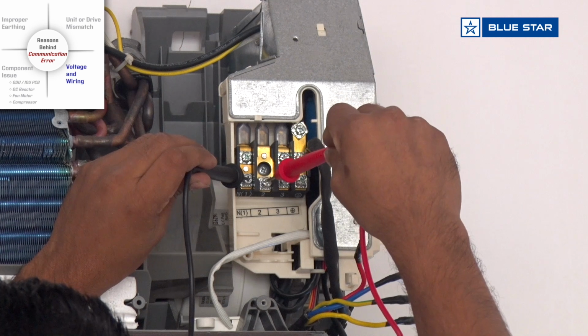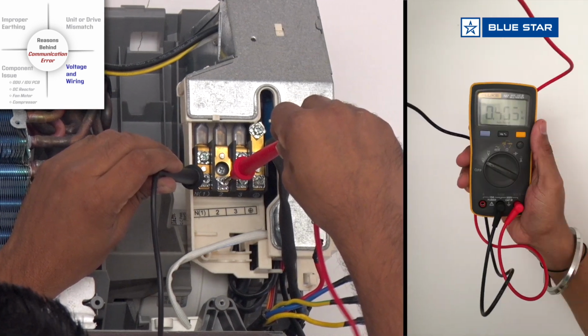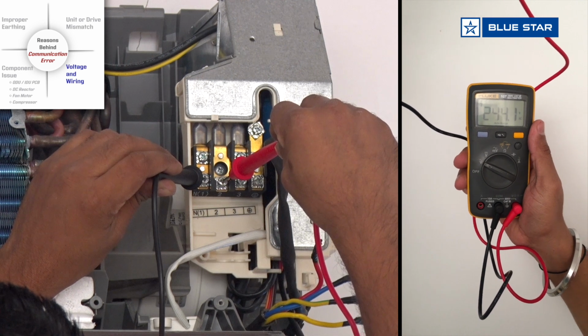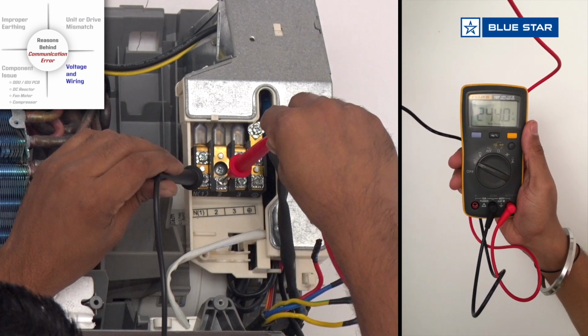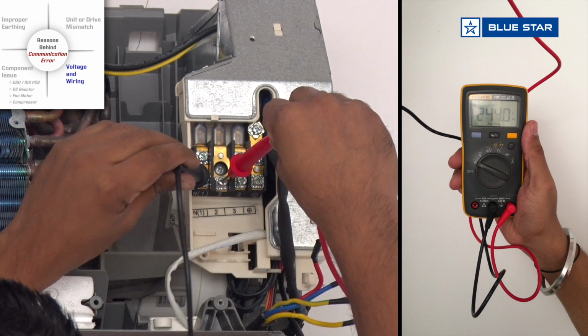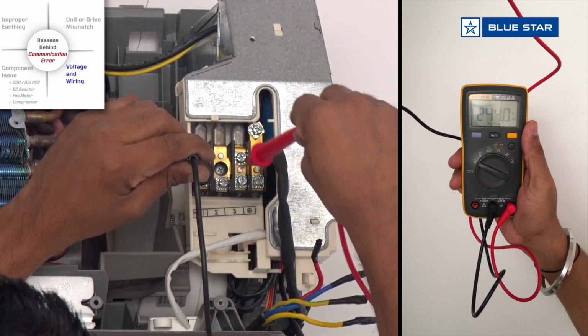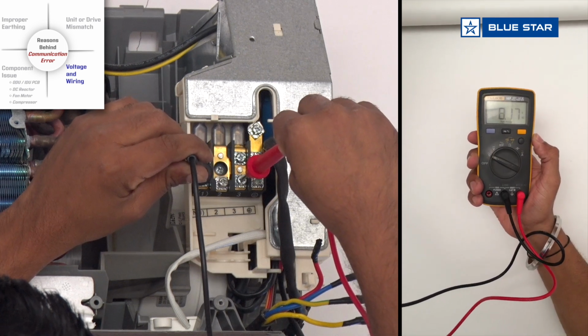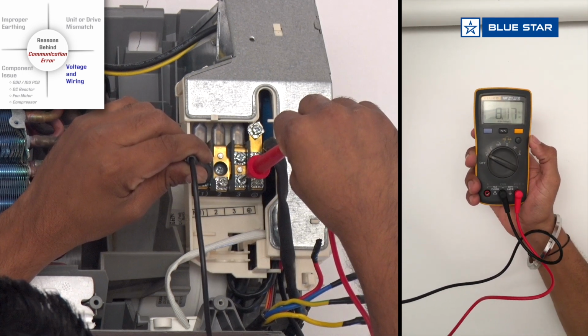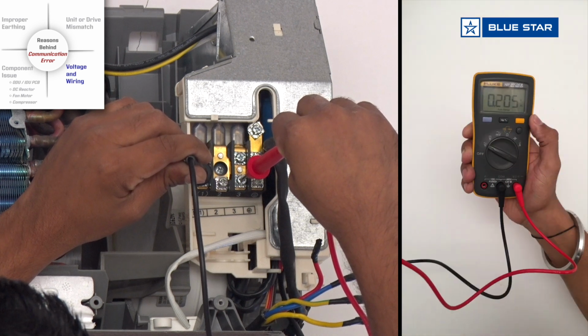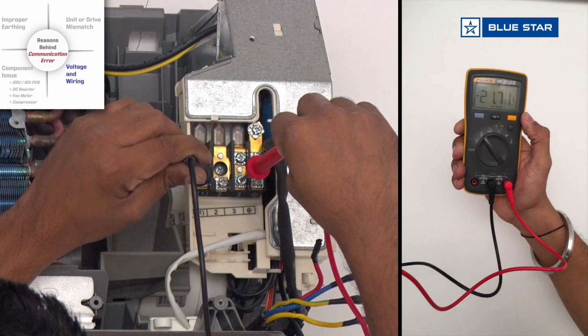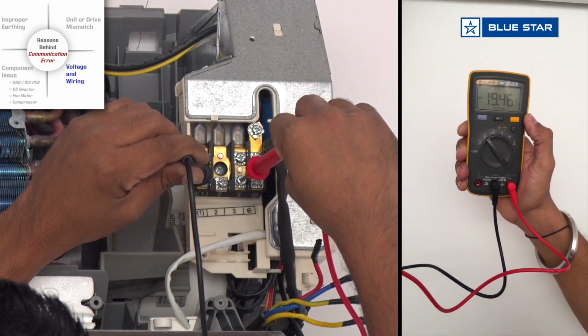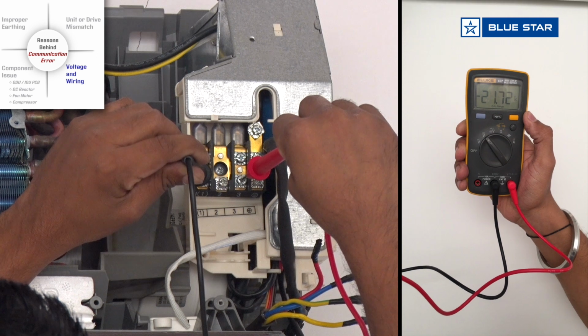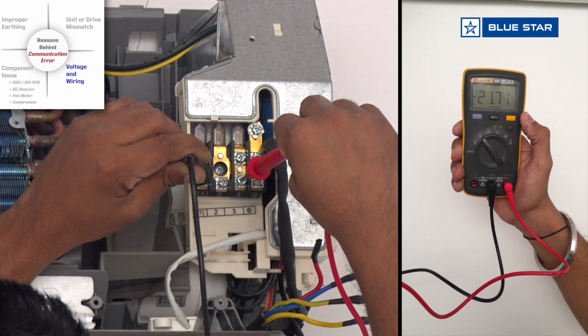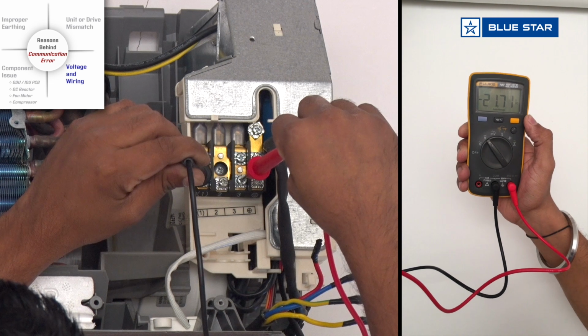In healthy condition, the IDU PCB will show a value between 220 to 240 AC volts, same as the input supply to the unit, between phase and neutral. Between neutral and signal, it will show a constant AC voltage between 0 to 12 volts and a constant DC voltage between 0 to 24 volts. If the voltage between neutral and signal is not constant, it means there is an issue with the IDU PCB and it needs to be replaced.